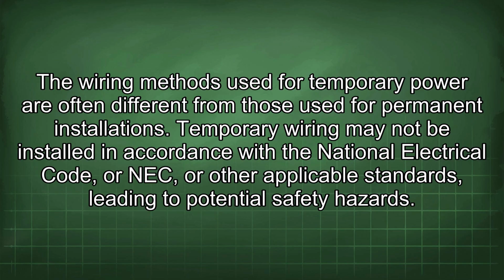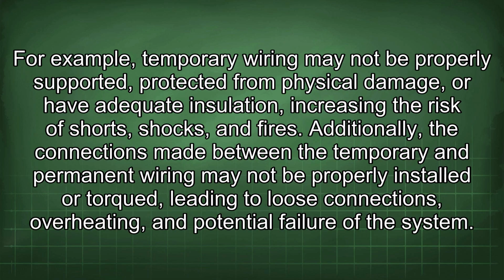Temporary wiring may not be installed in accordance with the National Electrical Code, or NEC, or other applicable standards, leading to potential safety hazards. For example, temporary wiring may not be properly supported, protected from physical damage, or have adequate insulation, increasing the risk of shorts, shocks, and fires. Additionally, the connections made between the temporary and permanent wiring may not be properly installed or torqued, leading to loose connections, overheating, and potential failure of the system.